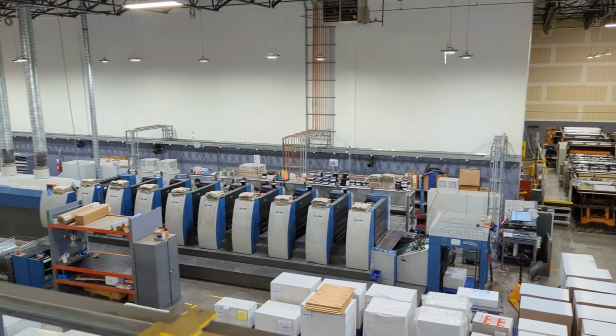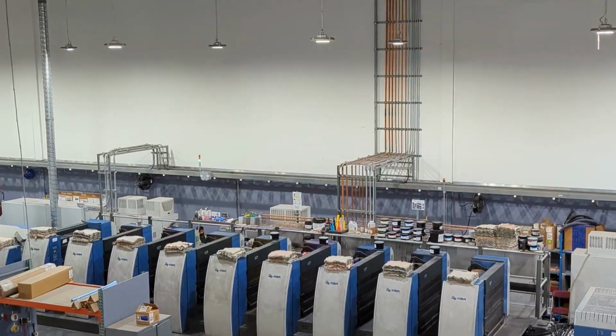We worked on 2 printer chillers this week. One of them was overheating and had some alarms on it. When we checked it out, there's a little paddle flow switch that gets pushed by the flow and sends a signal, and that paddle just wasn't working.